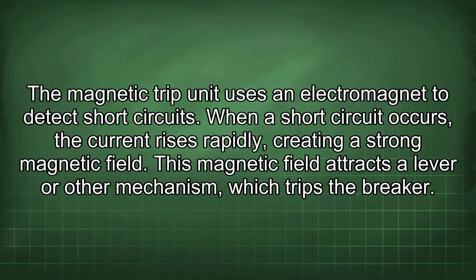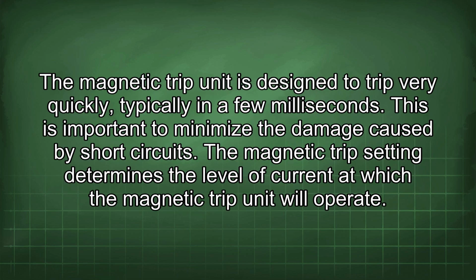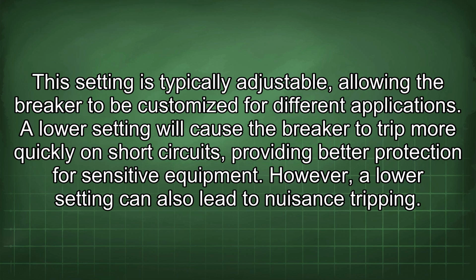The magnetic trip unit uses an electromagnet to detect short circuits. When a short circuit occurs, the current rises rapidly, creating a strong magnetic field. This magnetic field attracts a lever or other mechanism, which trips the breaker. The magnetic trip unit is designed to trip very quickly, typically in a few milliseconds. This is important to minimize the damage caused by short circuits. The magnetic trip setting determines the level of current at which the magnetic trip unit will operate. This setting is typically adjustable, allowing the breaker to be customized for different applications.